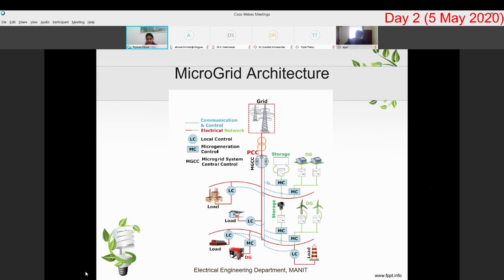All these controllers are connected via blue dotted lines, which are the communication lines, to a microgrid central controller. This microgrid central controller sends commands to all the individual controllers, be it the load controller or the individual generator controller, to operate in a controlled and coordinated way. What generator should dispatch what amount of power, what load should be there, and what load should be shed off — all that is decided by this MGCC.